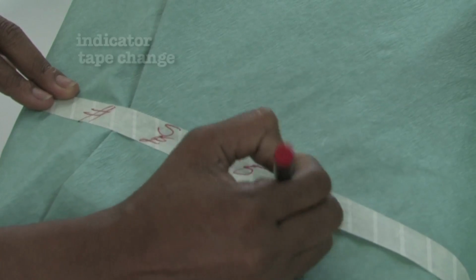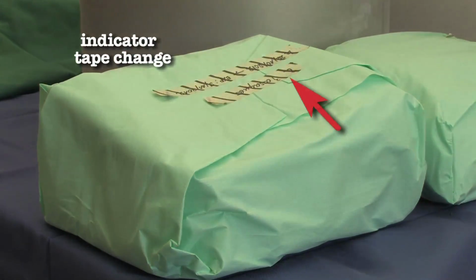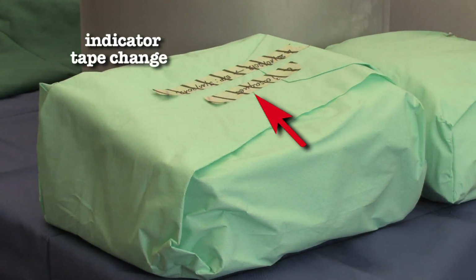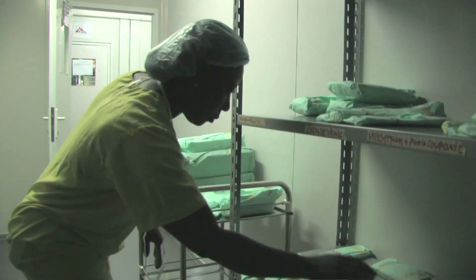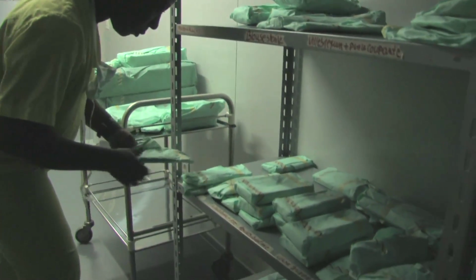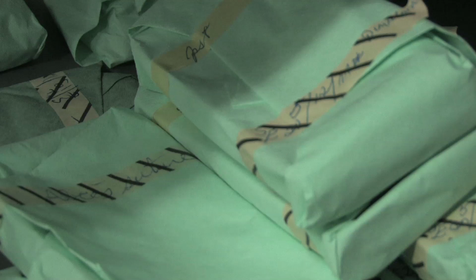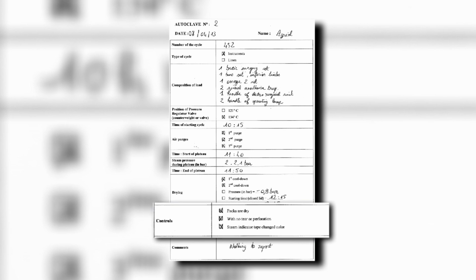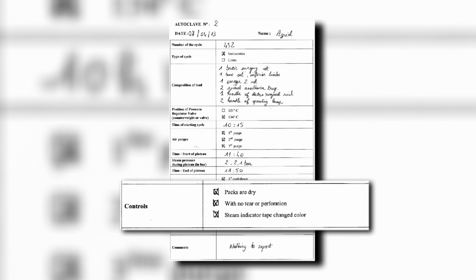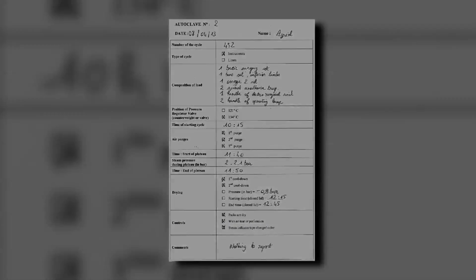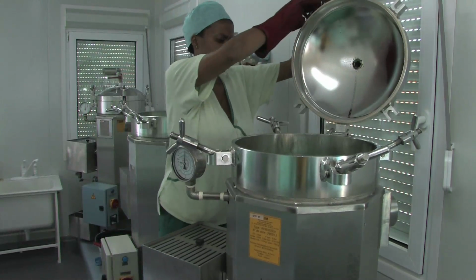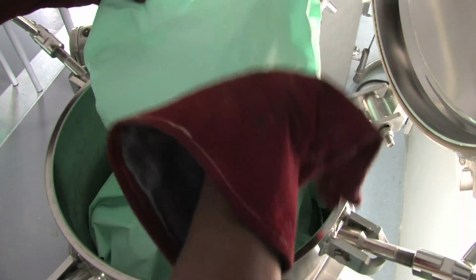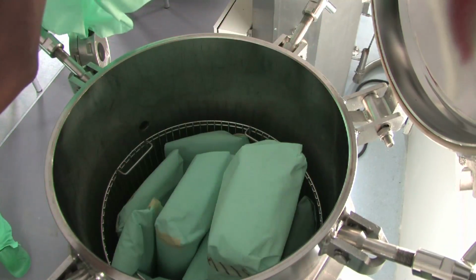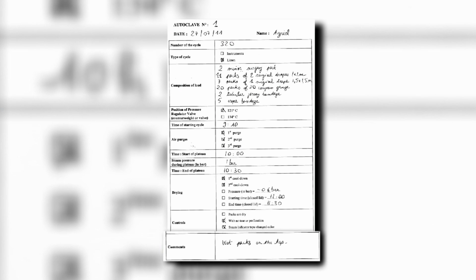3. After autoclaving, the autoclave indicator tape should show black stripes on a white background. This tape, which is readily visible, tells the operating room or treatment unit staff that the equipment has undergone an autoclave sterilization cycle and may be used. These checks should be entered on the cycle monitoring sheet. Checks whose results are satisfactory are marked off by the technician in charge of the cycle. Any problems observed during a cycle, such as packs that are wet when removed from the autoclave, steam escaping from the seal, or a power outage, should be noted on the cycle monitoring sheet.